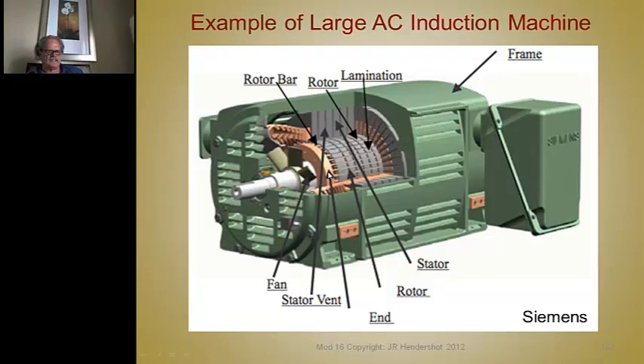These bars are extended because this rotor is so large. The thermal expansion rate of steel versus copper is so much different that copper expands more than steel per degree C. So what happens is, if this were right up against it, there would be tremendous stresses on the bar right at the intersection because the steel isn't expanding as fast as the bar. So you continually stress these bars to the point they'd work harden and eventually break. And we're going to talk more about that.